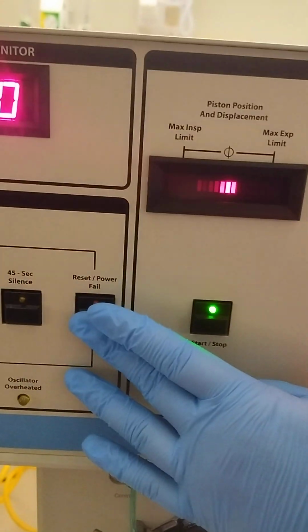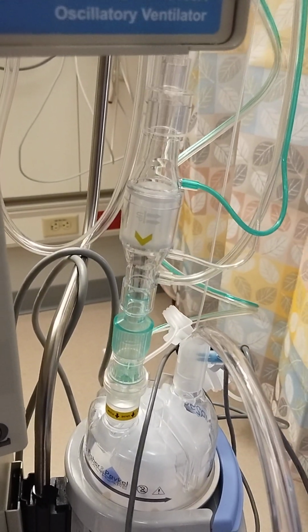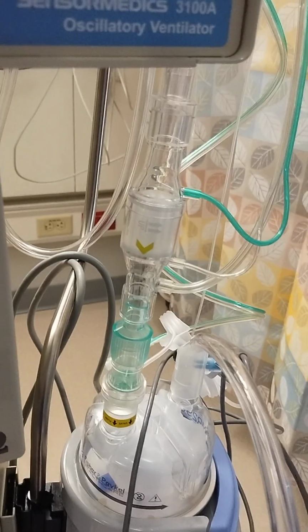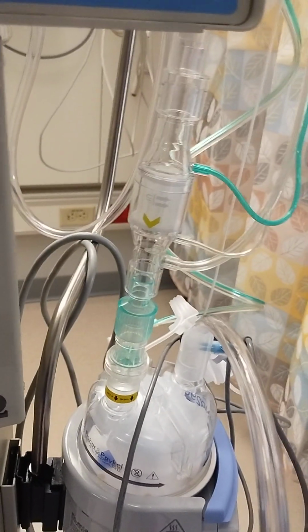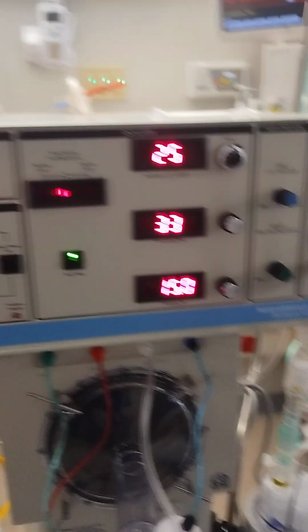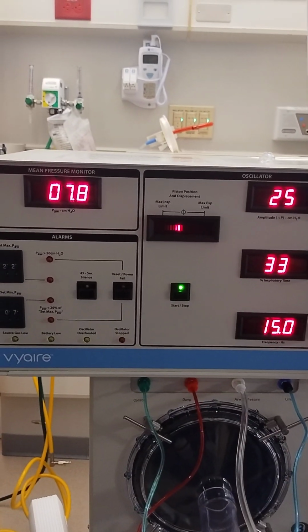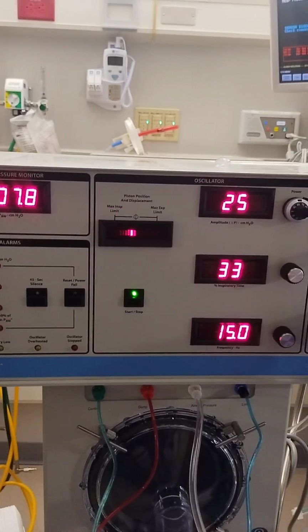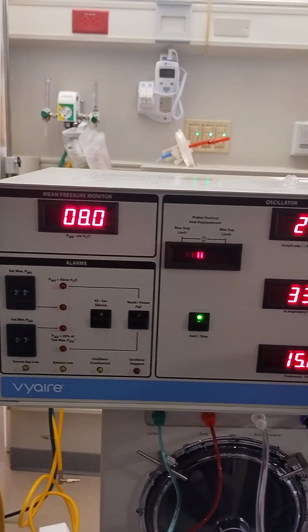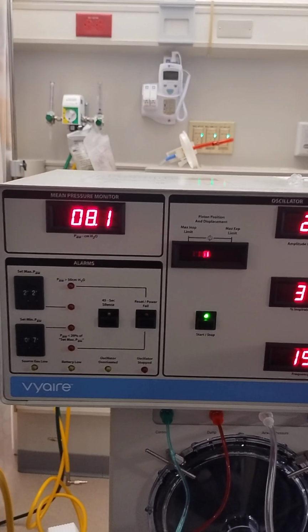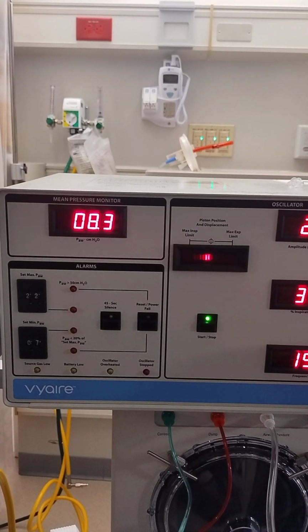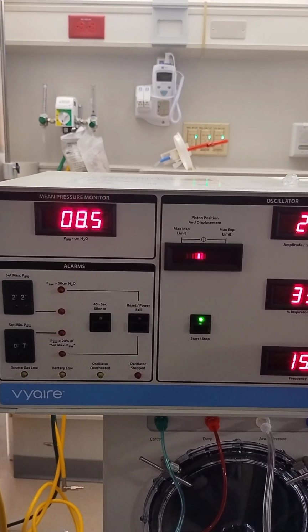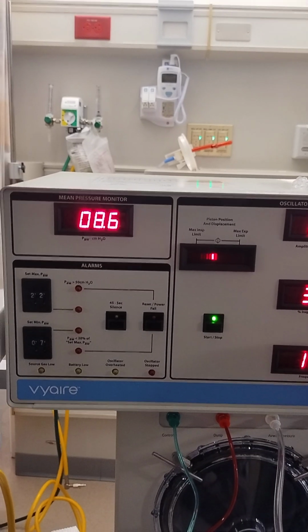Now we've placed it on the dry side. We're resetting our oscillator, so it just takes a moment to do that. And so we see here it's a little water on the dry side of our humidifier. We do need to make adjustments to our mean airway pressure because we've just added some additional parts. So we're going to adjust until we get back to the ordered mean airway pressure of 10. This is an example.